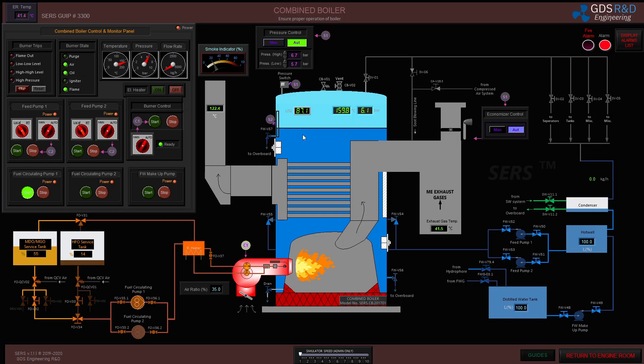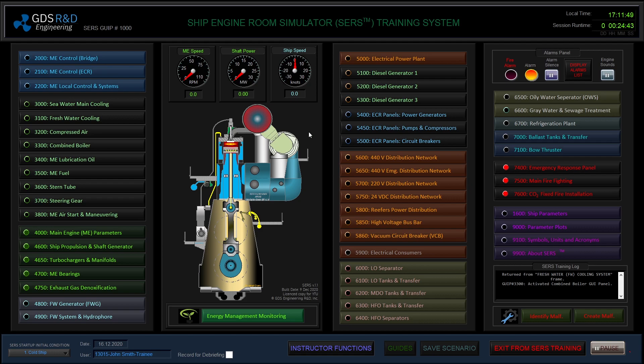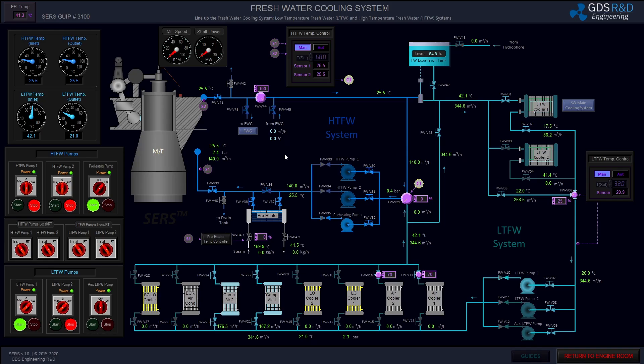I'm now switching back to the combined boiler. I will open the steam valve. These are the valves for each steam consumer — for example, separators, tanks, and other systems in the engine room. By opening these valves, I'm now able to supply steam pressure to the main engine preheater. I will open the outlet valve of the main engine preheater.